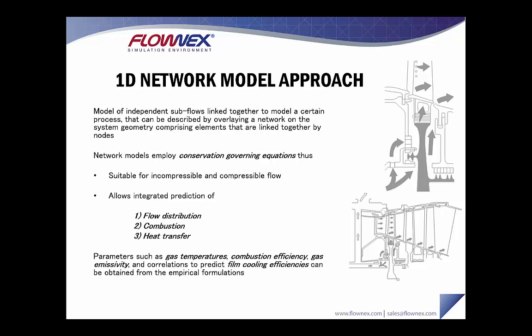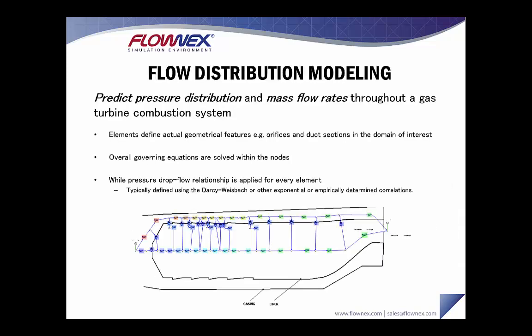Parameters such as gas temperatures, combustion efficiencies, gas emissivities, and correlations to predict film cooling efficiencies can be obtained from empirical formulations and implemented into the network. Flow distribution modeling allows you to predict the distribution and mass flow rates through the gas turbine combustion system. Typically elements define actual geometrical features such as orifices and duct sections in the domain of interest. The overall governing equations are solved within nodes, and a pressure drop flow relationship is applied for every element, typically defined using the Darcy-Weisbach, exponential, or empirically determined pressure loss correlations.